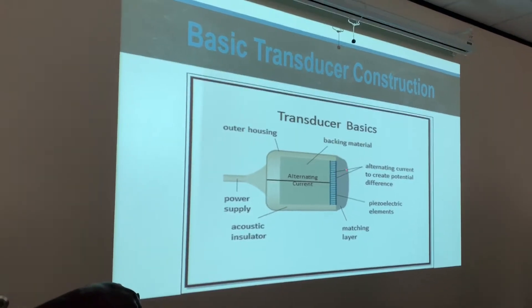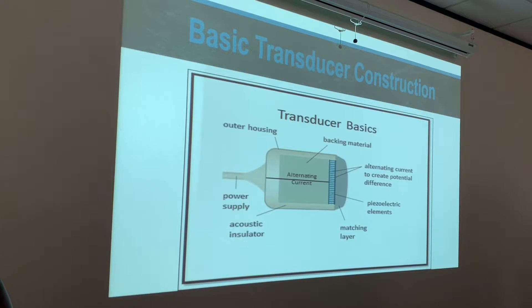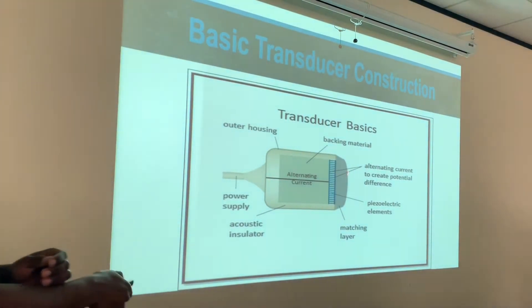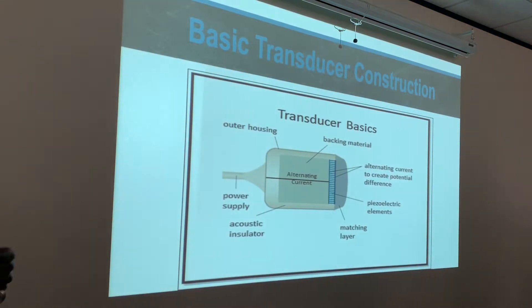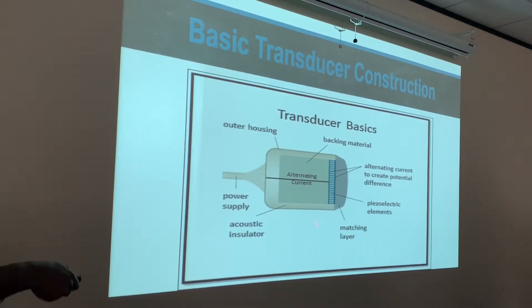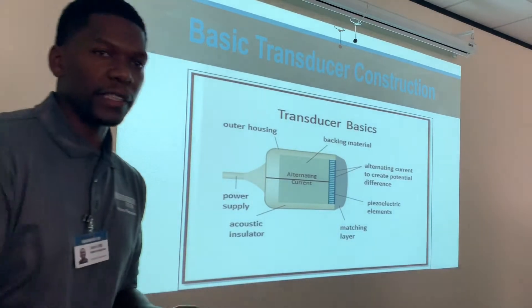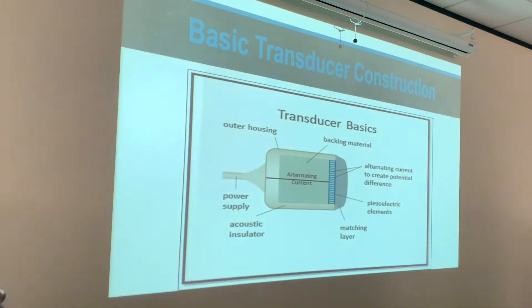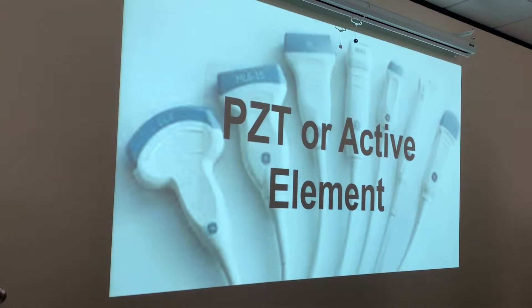That electrical current is going to cause vibration of the PZT and send out multiple sound waves. Sound waves are going to hit a structure, bounce back, and cause pressure and vibration against the PZT. The PZT is going to create an electrical signal going back to the power supply and back to the ultrasound system — transmission and reception. We have our acoustic insulator and our matching layer, which actually touches the patient. Our backing material is thick because we want the sound to stop as soon as possible — letting it keep ringing will degrade our image.